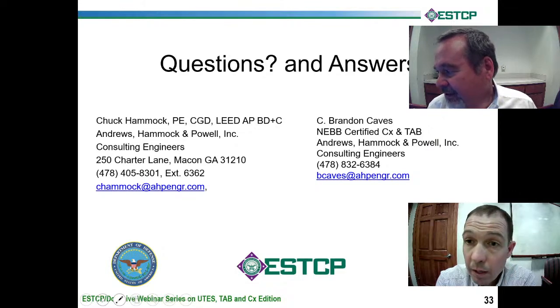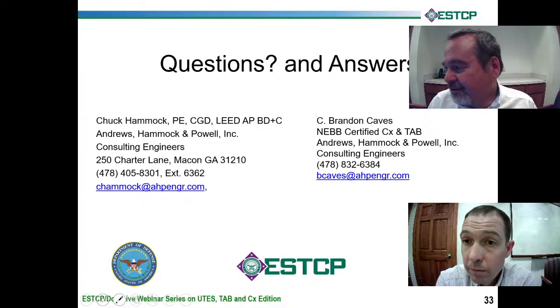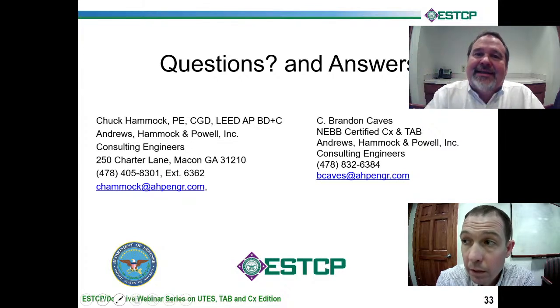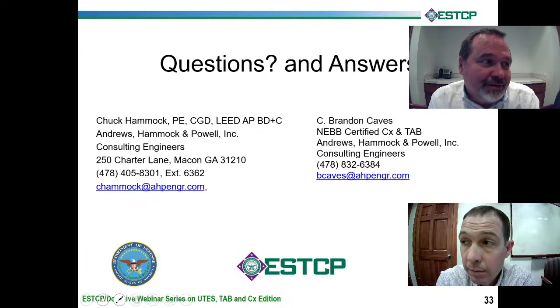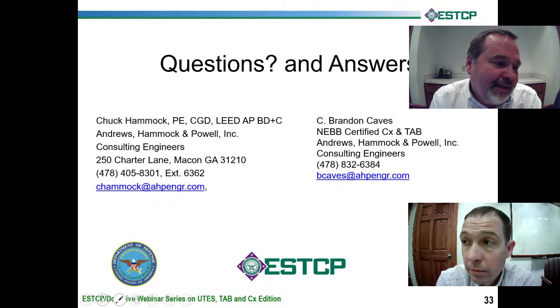What is the difference between TABing a conventional open loop geo system versus an ATES system, or a conventional closed loop versus BTES? What I'd like to say in regards to that is that what we like to call a BTES system is just a closed loop system on steroids, and an open loop system on steroids is ATES. So what does that even mean? Well, in conventional closed loop geothermal systems, you've got a ground loop heat exchanger out there. All the boreholes are piped in parallel, so you can't really differentiate between an interior borehole that might be good for storage or an exterior borehole that's maybe better for dissipating heat or extracting heat.